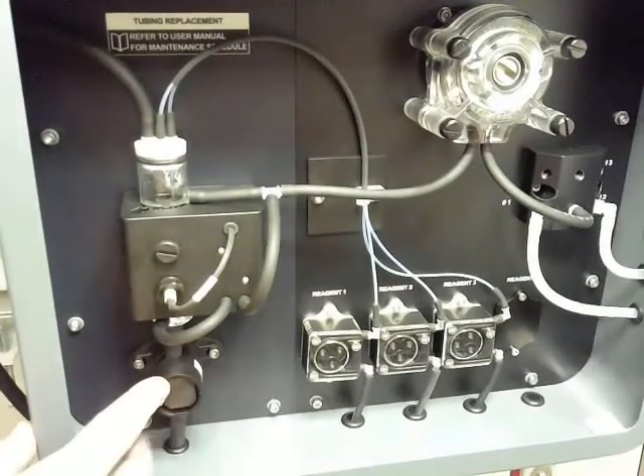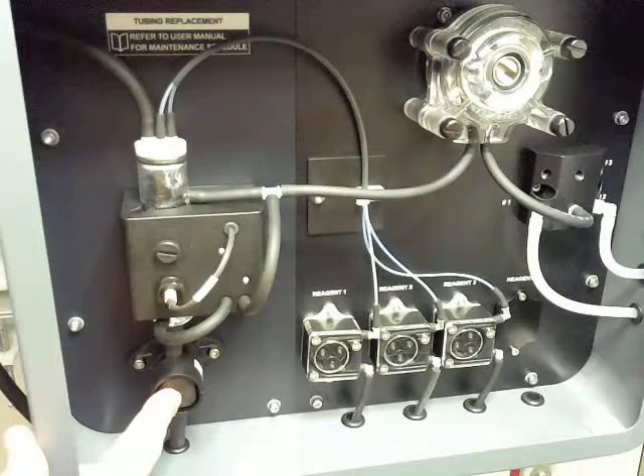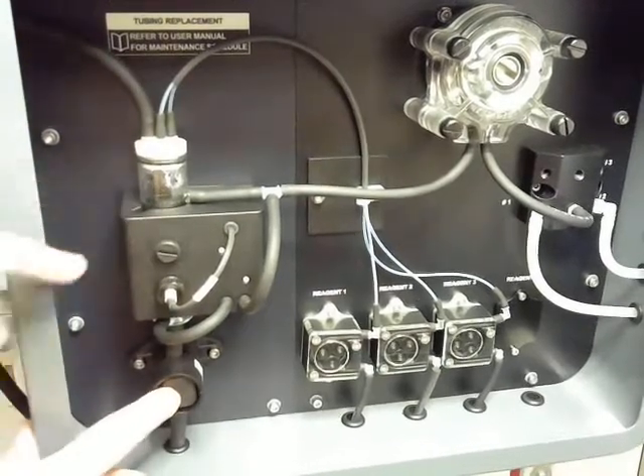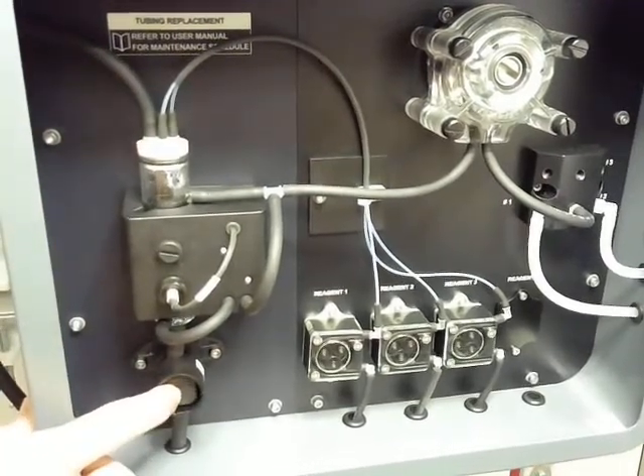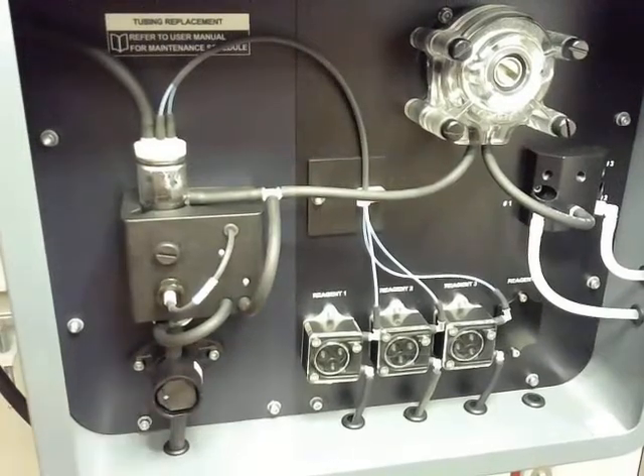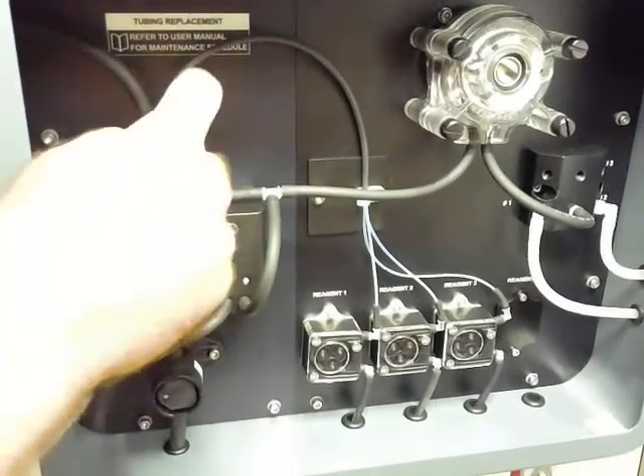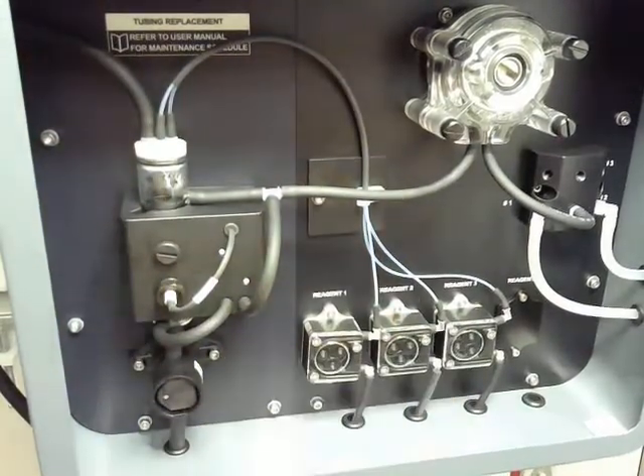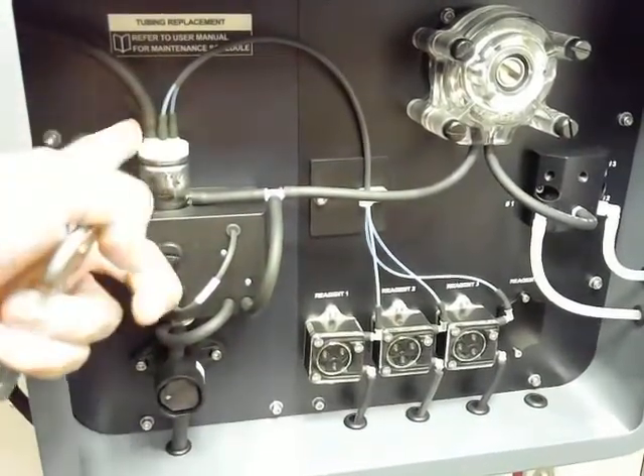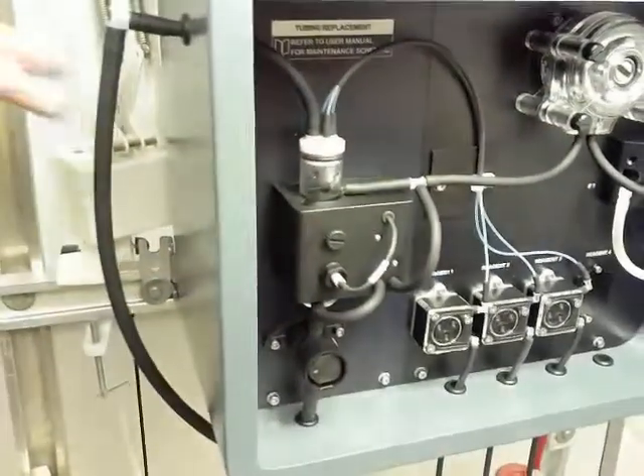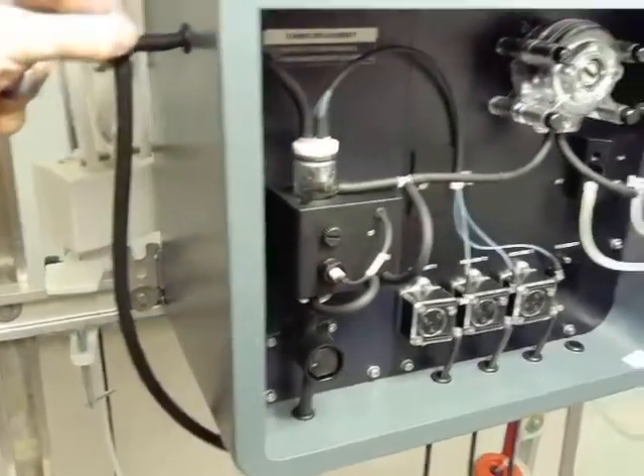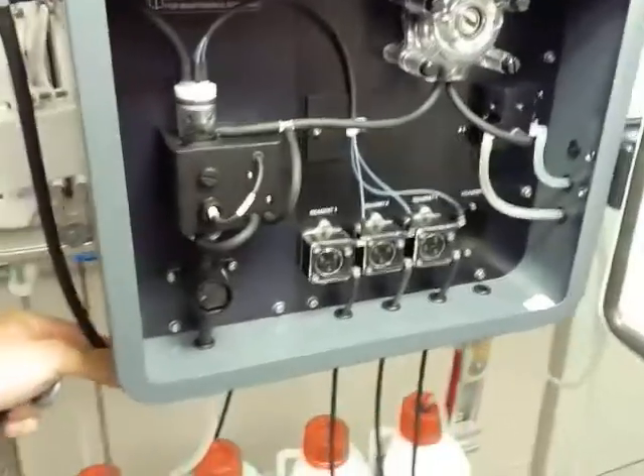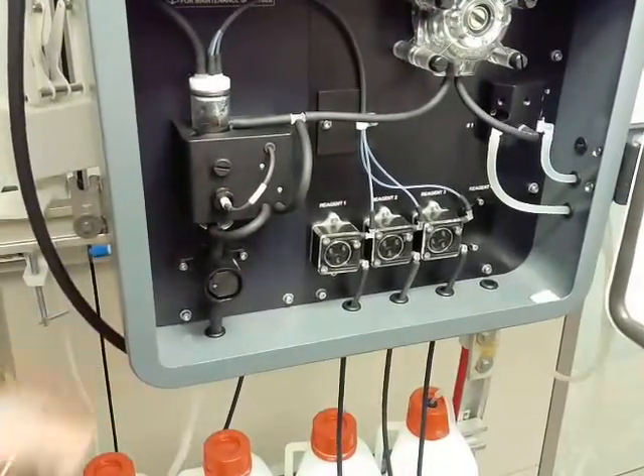The pinch valve drain here. If you were to manually push this in, you'd see our flow cell empty out of all of its sample and drain out the bottom. Same thing happens when that valve is electronically activated: it just opens up and drains out anything that's in there. These are our tubings that go to our reagent pumps. This overflow tube here is tied into the outside, which is just a drain vent, which ties to our drain on the bottom of the analyzer that just goes out to waste.